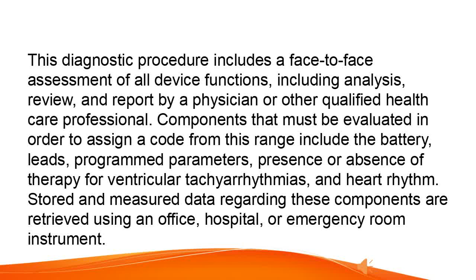This information is assessed to discern battery voltage, lead impedance, and settings for rhythm treatment and tachycardia detection, as well as to determine the defibrillator's current programming. If necessary, the sensing value and rate response, upper and lower heart rates, AV intervals, pacing voltage, and pulse duration, and diagnostics are adjusted. Ventricular tachycardia detection and therapies may also be altered. These codes include physician or other qualified healthcare professional review, interpretation, and report, and are assigned per procedure.